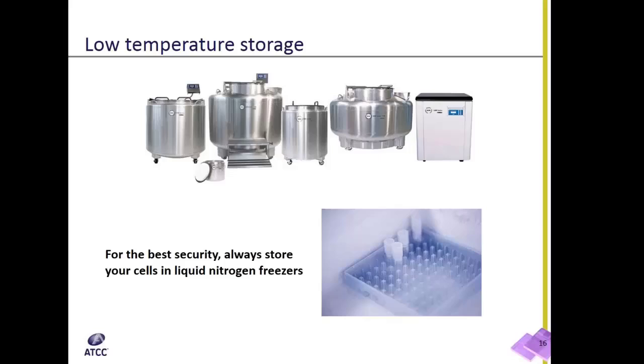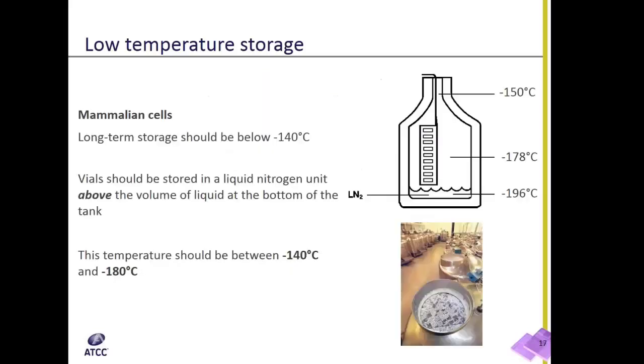For storing biological material at these low temperatures, it is highly advisable to use liquid nitrogen containers. There are two basic types of liquid nitrogen storage practices. One is immersing the vials directly in the liquid. The other involves holding the vials in the vapor phase above the liquid.